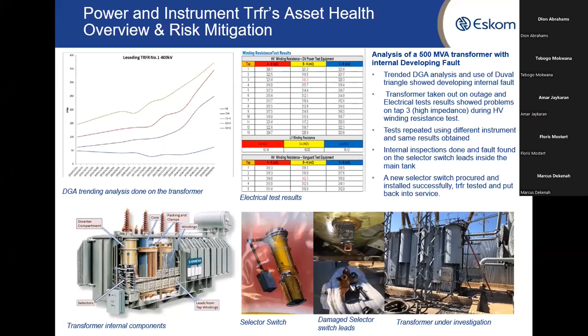We then had to do electrical tests on this transformer, and you could see that using two different methods, because before you can do internal inspection, which costs a lot of money, you need to be sure that there's definitely a developing fault inside this transformer. So using two methods, you could pick up that there's a problem on the selector switch, and then this asset that is worth way over 40 million, we could then inspect it, pick up the fault, order a new selector switch, and replace it and put the transformer back into service at a cost of around 4 million, saving the business more money, as well as ensuring that we don't experience environmental incidents. Because as transformers fail, you have oils that get taken out, and in most cases, they can safely go out to your oil dams.